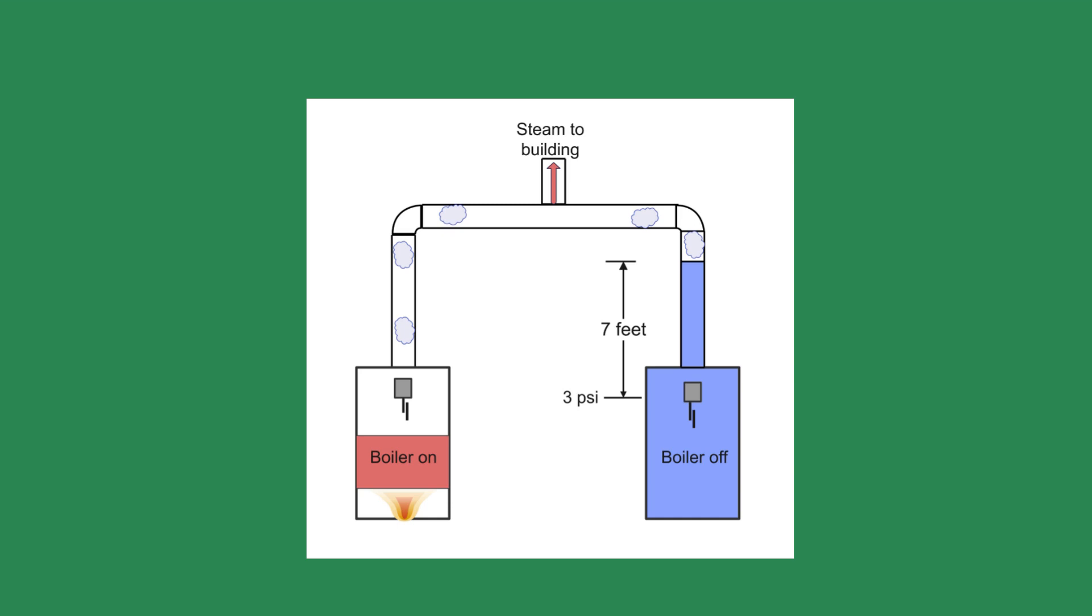In this system, the steam from the firing boiler filled the idle boiler. The steam condensed back to water inside the lag or idle boiler. Since the water was trapped inside, the level kept rising.